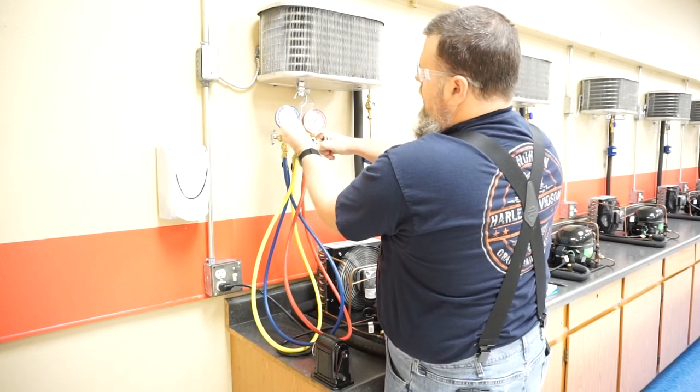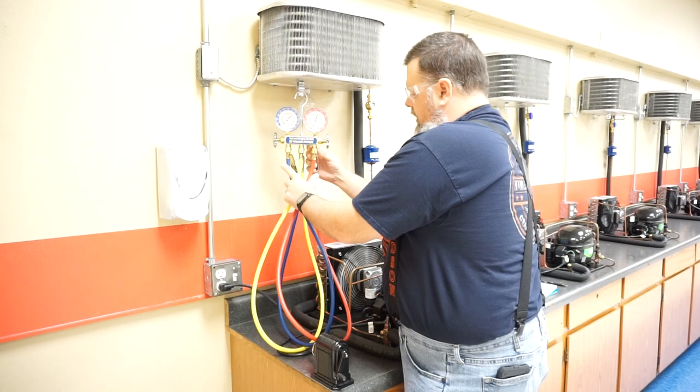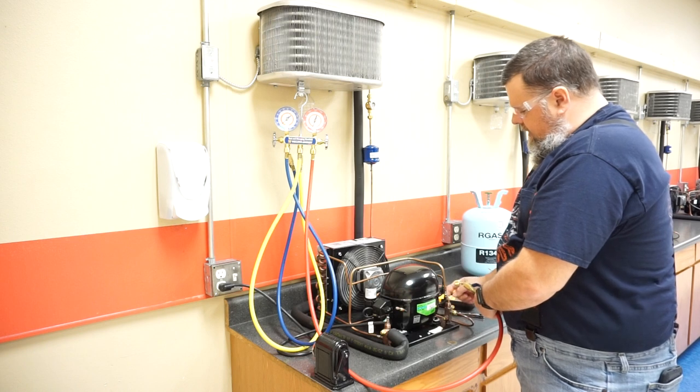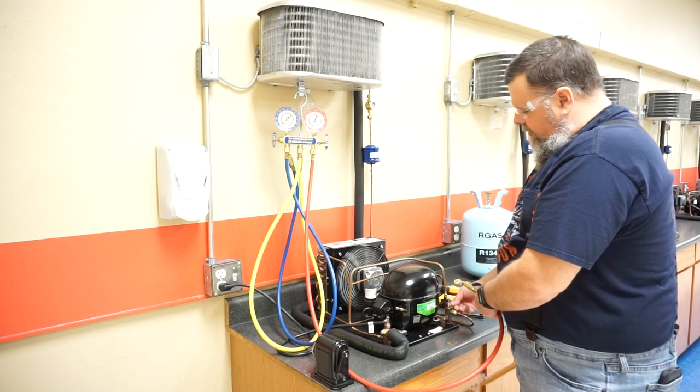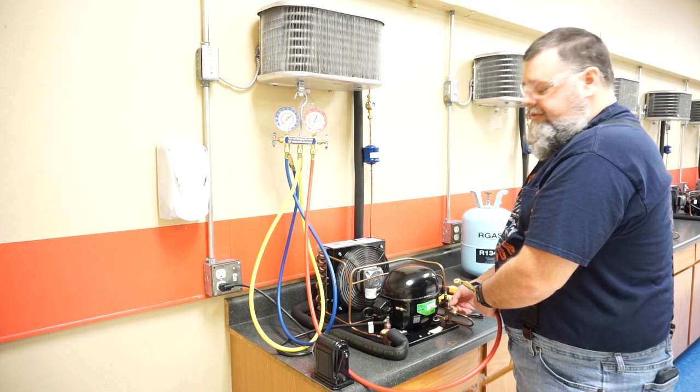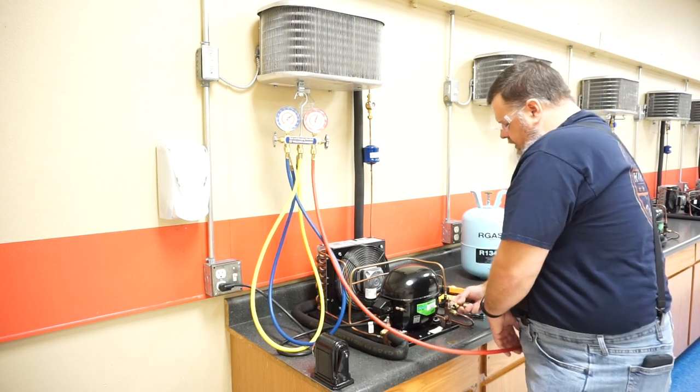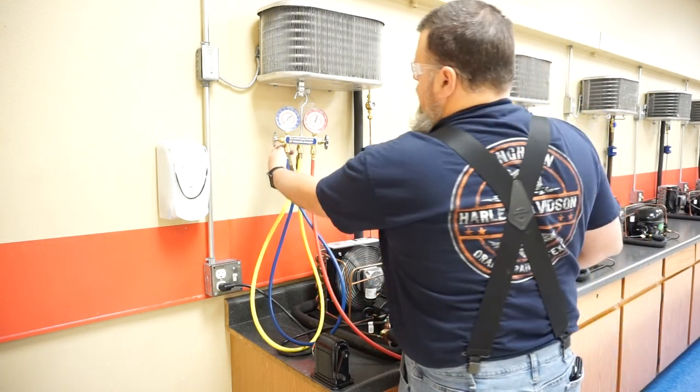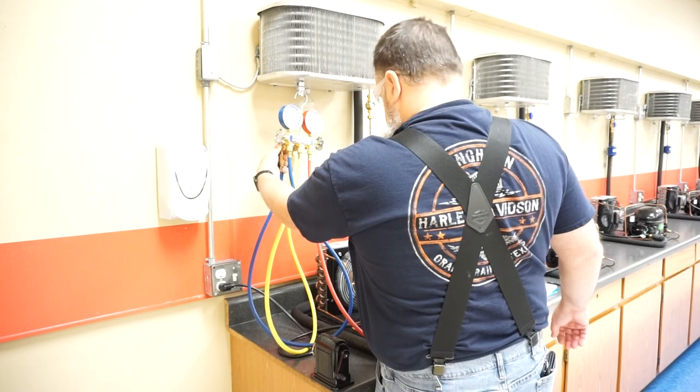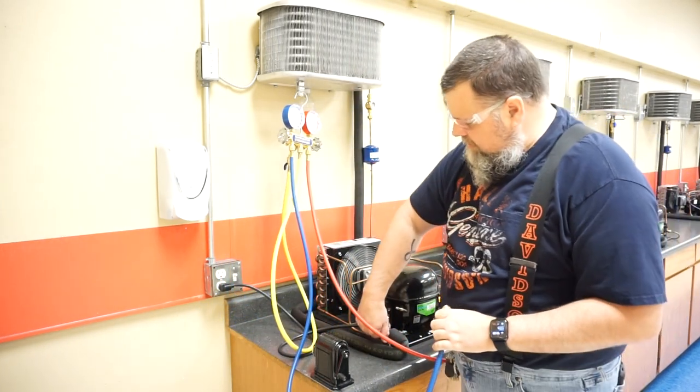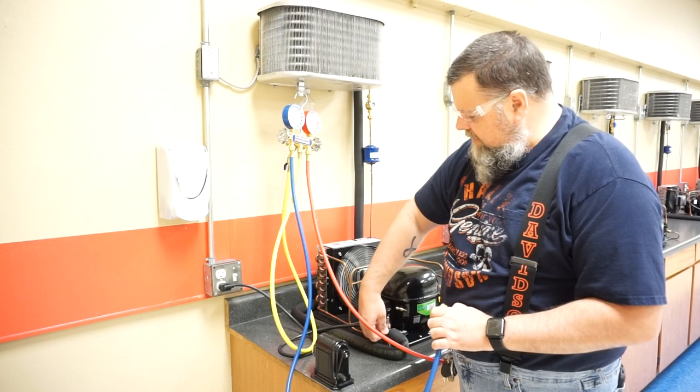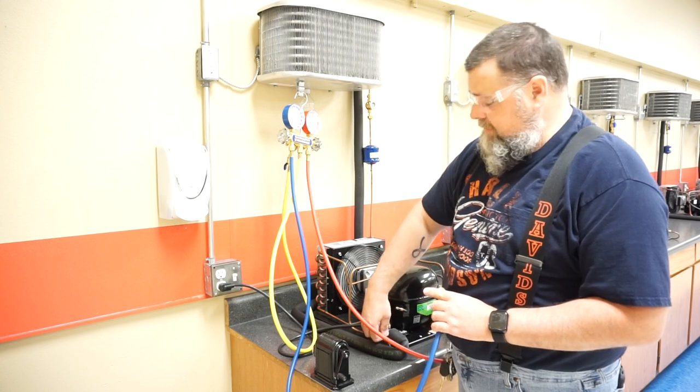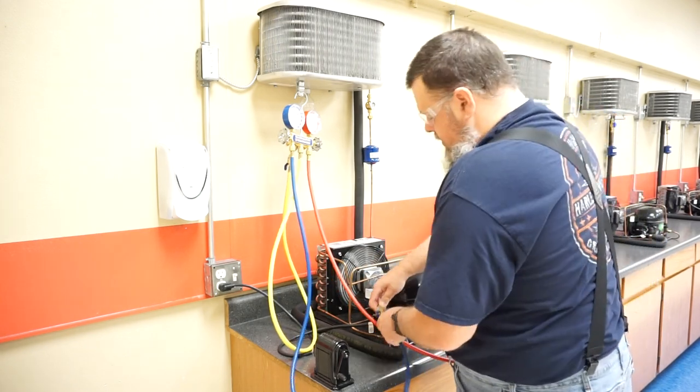I have my compound gauge and my high pressure gauge. Let's go ahead and hook up here. Check to see this is in the back seated position. I don't see anything or feel any pressure or hear it, so I think it's safe we can go ahead and take that off. Now let's hook up our suction side. Same thing, I want to be careful when I'm taking this off. If I hear any kind of hiss or feel pressure or see refrigerant, I need to make sure that this stem is seated well.